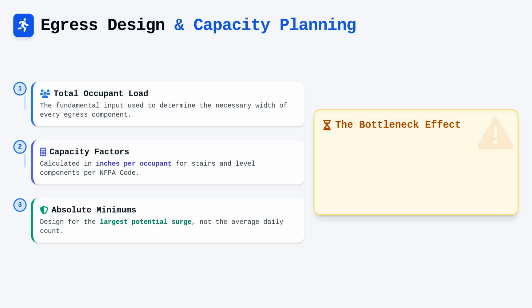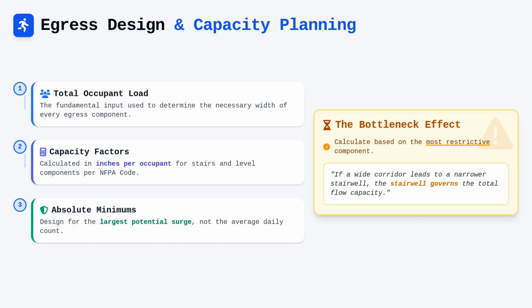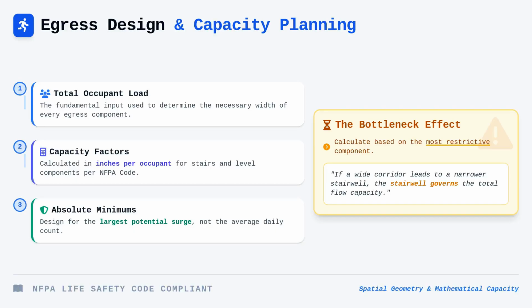A common error involves ignoring the bottleneck effect where multiple corridors converge into a single exit access point. Therefore, you must calculate the capacity based on the most restrictive component in the path. If your egress path transitions from a wide corridor to a narrower stairwell, the stairwell governs the total flow capacity of that entire section.